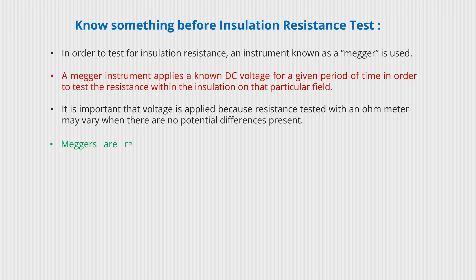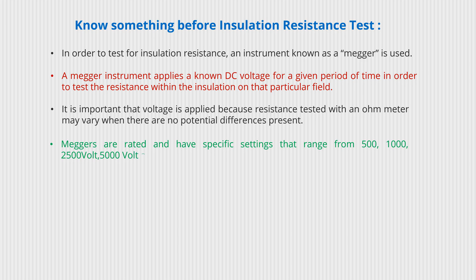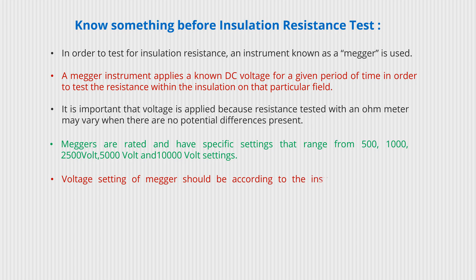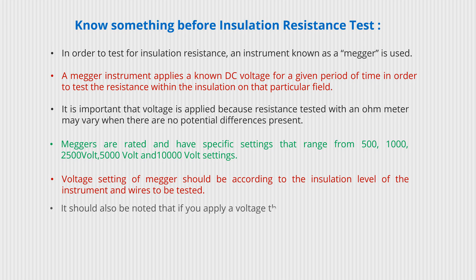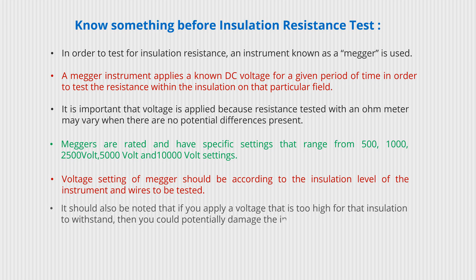Meggers are rated and have specific settings ranging from 500 volt, 1000 volt, 2500 volt, 5000 volt, and 10,000 volt settings. The volt setting of the megger should be according to the insulation level of the instrument and wires to be tested. It should also be noted that if you apply a voltage that is too high for that insulation to withstand, you could potentially damage the insulation.